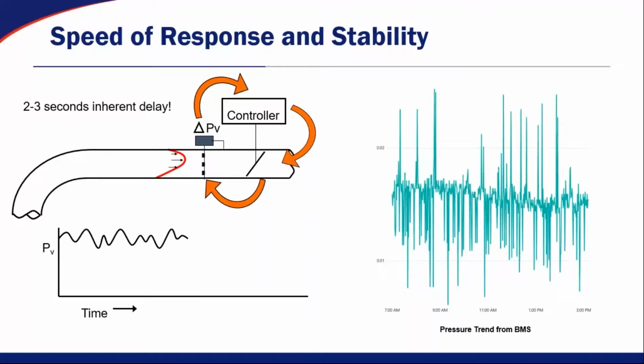And again, that's what you can see on the right-hand side of the screen with that blue chart. It's looking at a flow reading of a device over time, or pressure trend of the room. So every time that blade damper moves back and forth, the pressurization is going to change inside of that space. Now, if you want better controllability of that space, you can obviously slow down the PID loop inside that device and give it a more deliberate motion. That will give you much better stable pressure control, and it won't hunt as often.